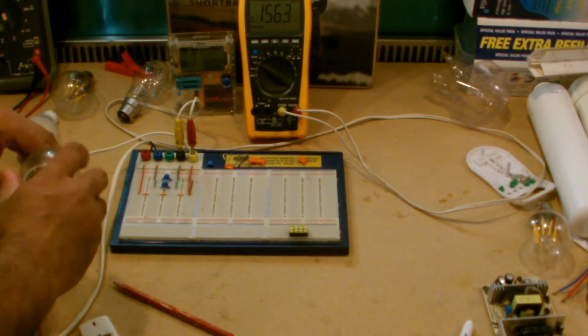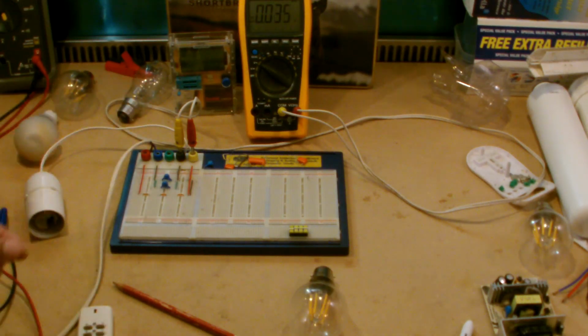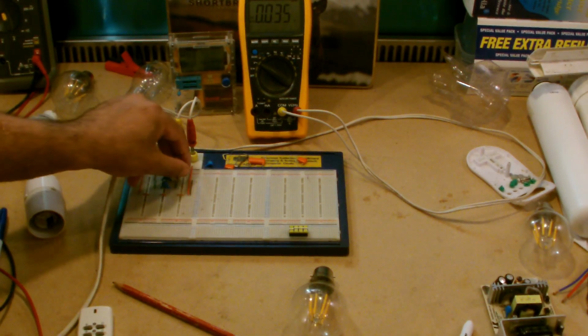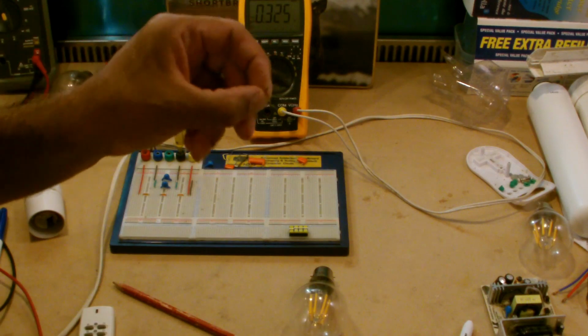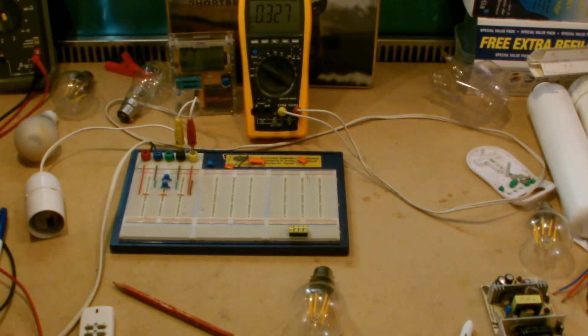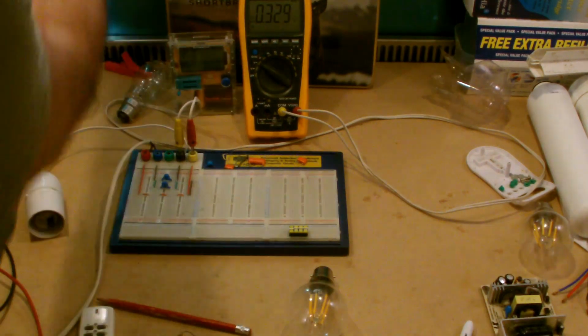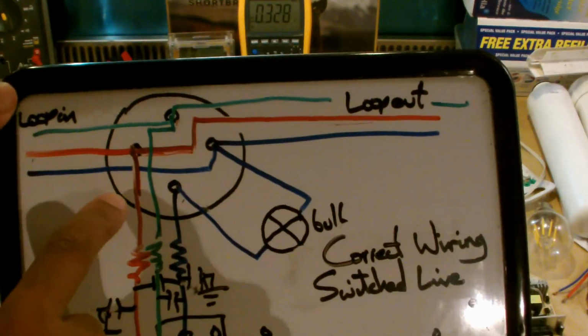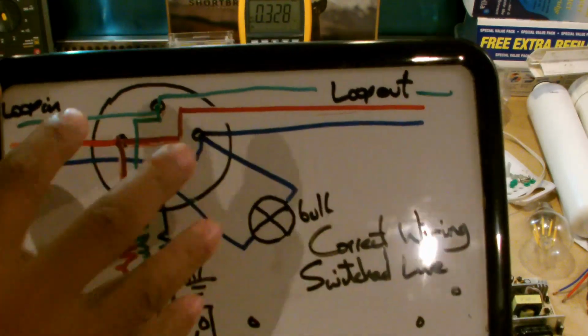but it's not lit. Now, this is the part where it seems like a lot of people are blindsided. Manufacturers do put the shunt, they use a shunt capacitor as opposed to a shunt resistor. You have to shroud this, and where you put it is quite important. So, for instance, a lot of people tend to put these shunts in this location, and this is the junction box with your main wiring.